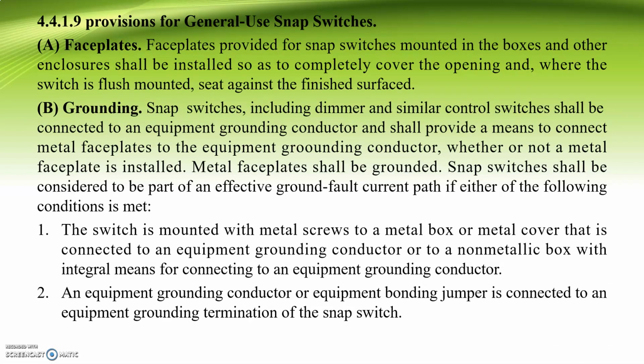Chapter 4.4.1.9, provisions for general use snap switches. A, faceplates. Faceplates provided for snap switches mounted in boxes and other enclosures shall be installed so as to completely cover the opening and, where the switch is flush mounted, seat against the finished surface. B, grounding. Snap switches, including dimmer and similar control switches, shall be connected to an equipment grounding conductor and shall provide a means to connect metal faceplates to the equipment grounding conductor, whether or not a metal faceplate is installed. Metal faceplates shall be grounded.